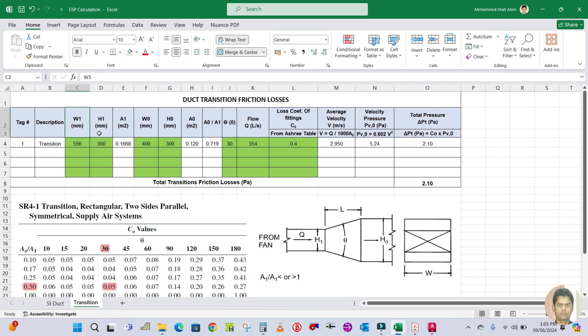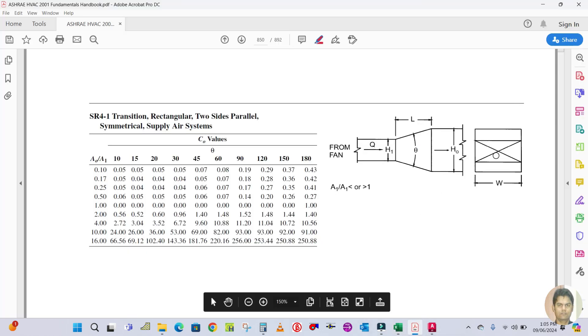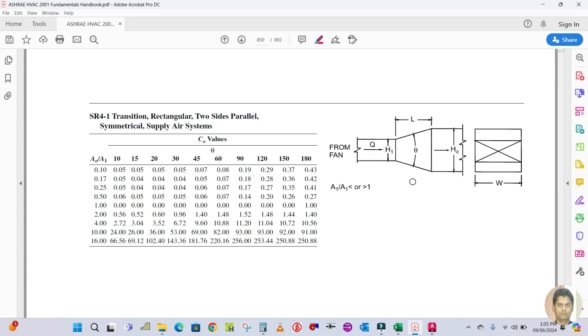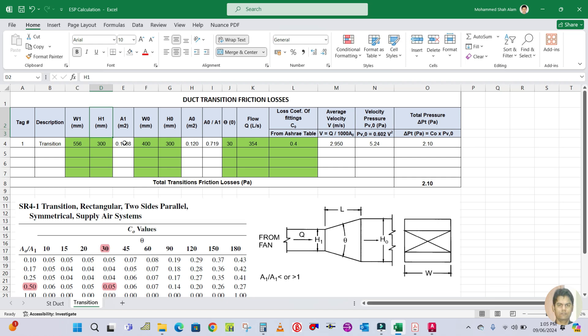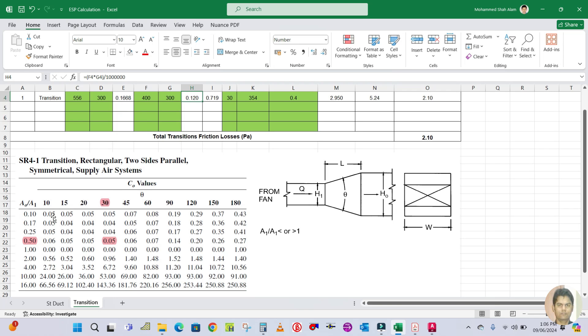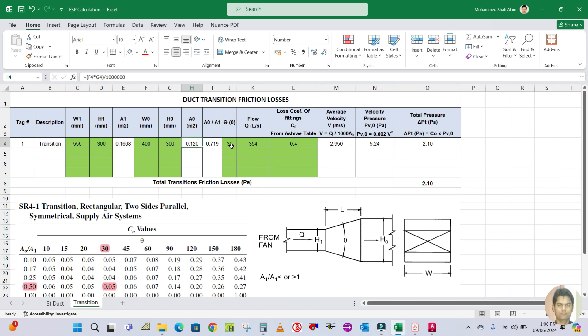Width one and height one refer to the entering side - the side from the fan. Width zero and height zero refer to the discharge side. A1 is the area calculated by multiplying width one by height one, and A0 is calculated similarly by multiplying width zero by height zero. The ratio A0 by A1 is required to look up the value from the chart table.